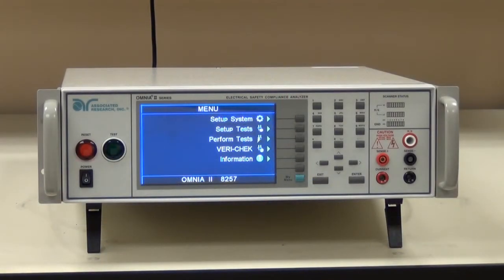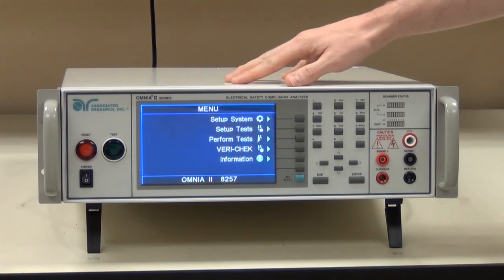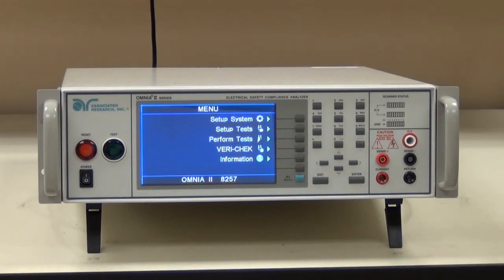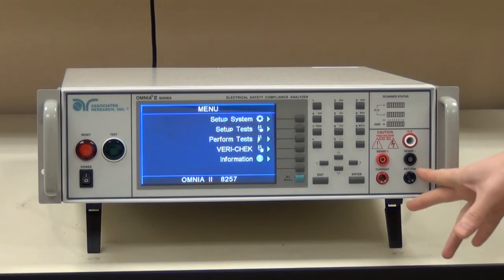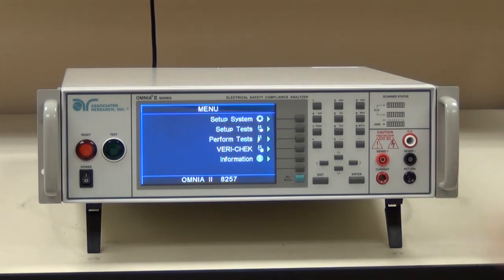One of the most frequent causes of damage to Associated Research Inc. instruments, including the Omnia series, is due to improper test station setup. We've determined that in many instances, test operators mistakenly allow high fault currents to feed back through the return input of their device. This causes damage to sensitive components and PCB traces. Fortunately, it's very easy to prevent this type of damage to your instrument by taking some simple considerations into account prior to testing.